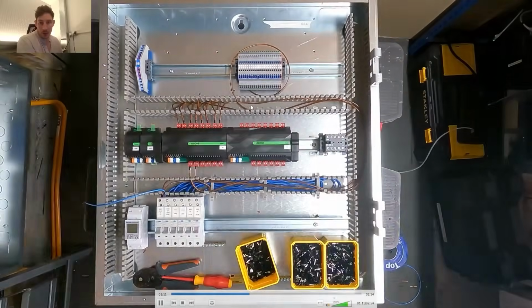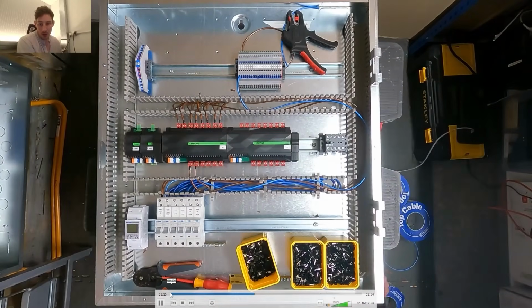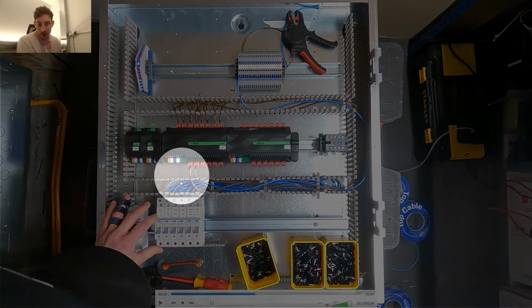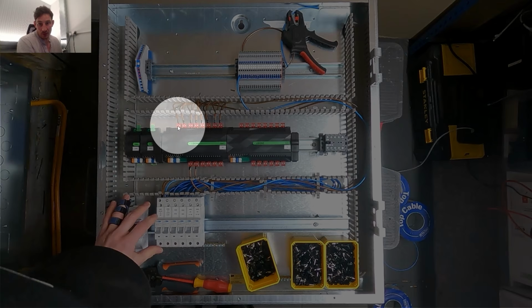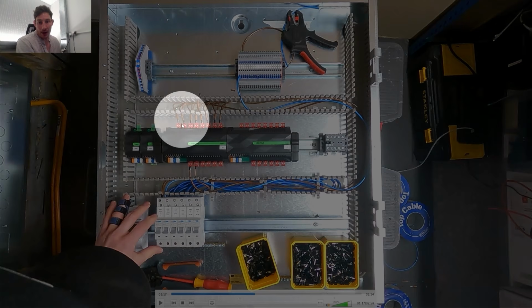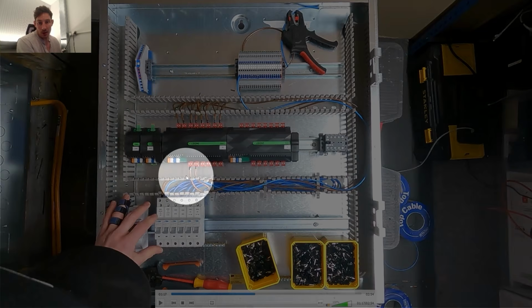So again, we're continuing the loop, the feed from RCBO 1, from the supply side of the relay, double ferrule out, in, out, in, out, all the way to the last one on this row, around here. I think we're using another RCBO to supply these ones.